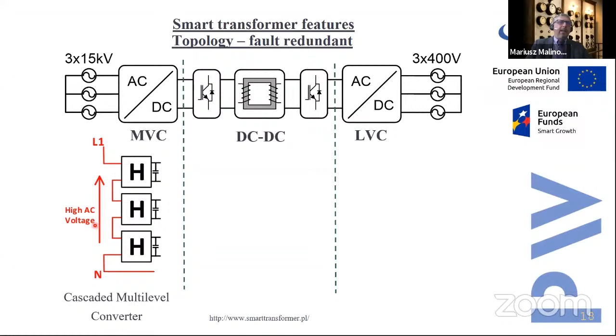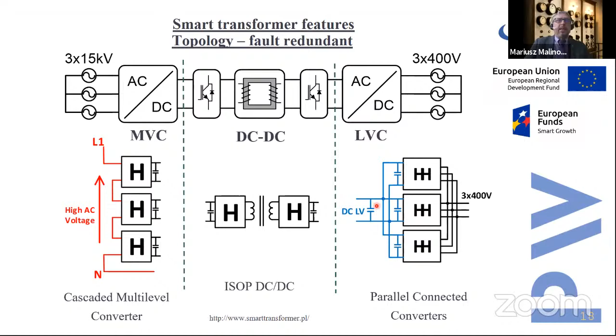Then we have the DC-DC conversion, which transforms the voltage from medium voltage to low voltage, based on an input series output parallel configuration, including the high frequency transformer. And we have DC-AC low voltage conversion, where the converters are parallel connected, because it demands high current on the low voltage side.